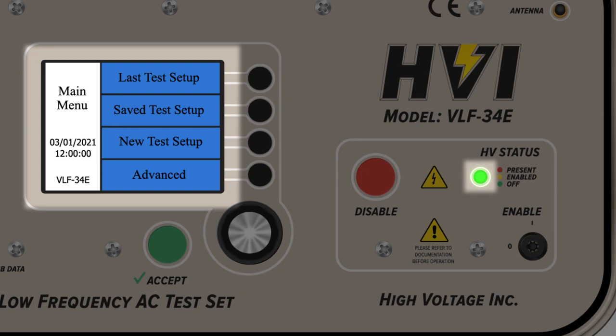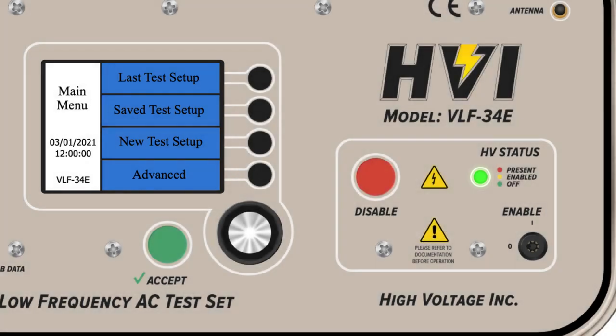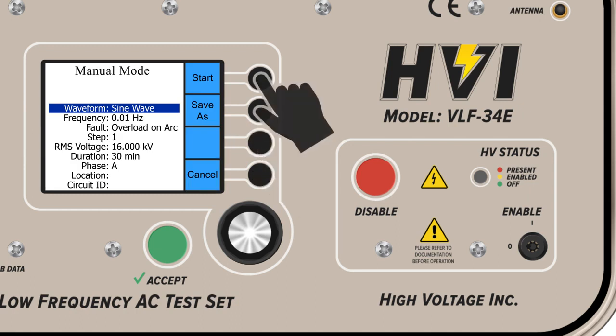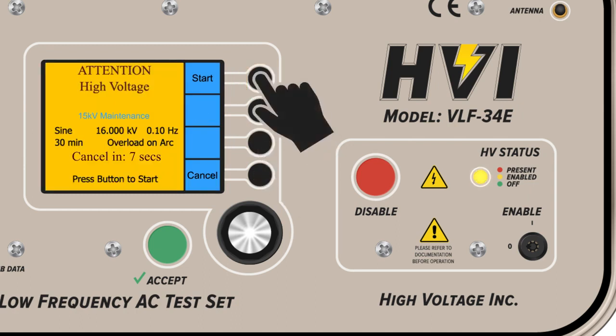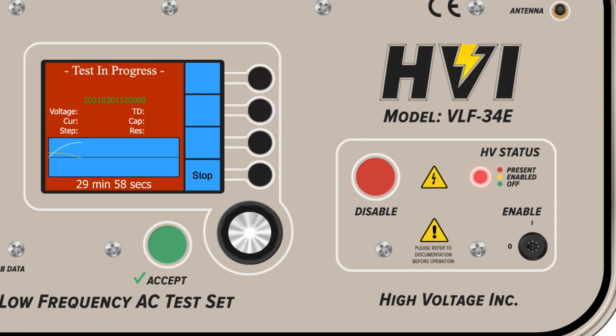The high voltage status light continually indicates to operators the current status of high voltage circuitry and capabilities within the device. Green for off indicates the device is on, menus operable, but no high voltage circuitry has been enabled, or that the voltage on the device under test, or DUT, is less than 200 volts. When the yellow, or enabled, light illuminates, it means that high voltage will soon be generated. A red light indicates high voltage is present. Follow all local and workplace safety standards.